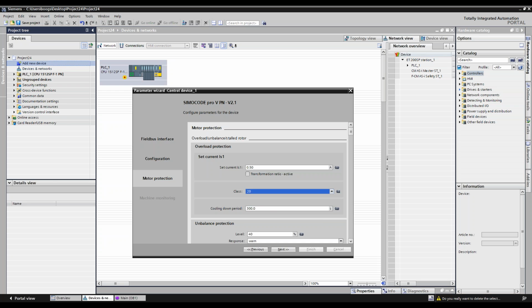But for my case, I'm going to go to trip class 20. So that's what trip class is. There's a lot more to it. I'm just giving you the quick rule of thumb. All right, cooling down period. Because it is a solid state overload, it requires cool down, but nothing like the old style starters.